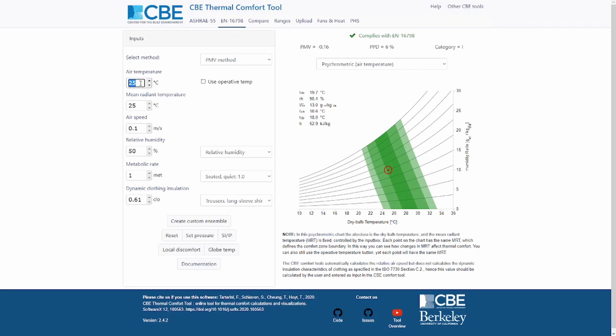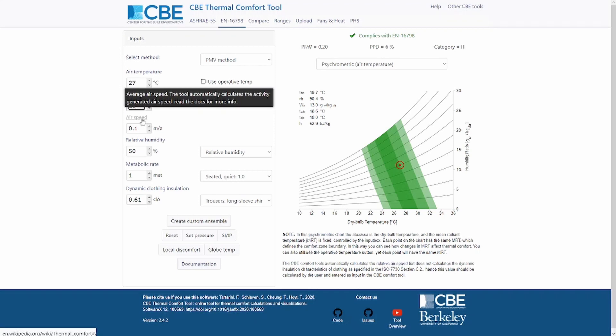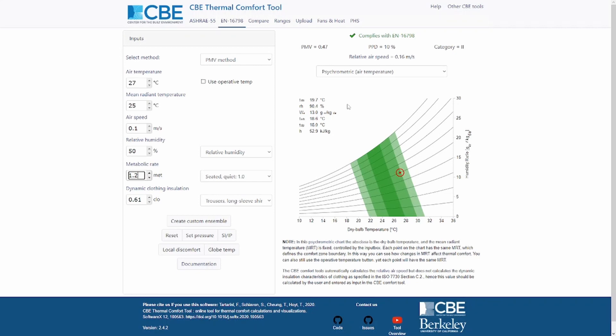As you change the values, the results are updated automatically. Please note that the air speed you enter here is the measured air speed — the tool automatically calculates the activity-generated air speed. For metabolic rates higher than one, a new output appears: the relative air speed, which accounts for the self-generated air speed of a moving person, as movement causes slightly higher experienced air speed than what was measured.